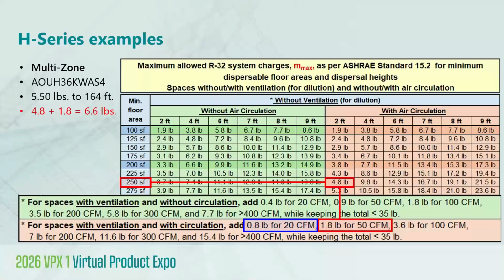But if you look to the left of that 1.8 pound entry, in the blue box, I highlighted that because instead of 50 CFM, what if we introduced 20 CFM? So that adds 0.8 pounds, which brings it up to a max allowable charge of 5.6 pounds. So by definition, 5.6 pounds is greater than the 5.5 factory charge, but it's pretty close. And, practically speaking, I don't think there's going to be much difference in cost to facilitate 50 CFM instead of 20. So in my opinion, it's always best to favor on the side of safety.